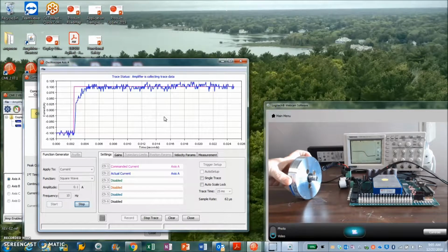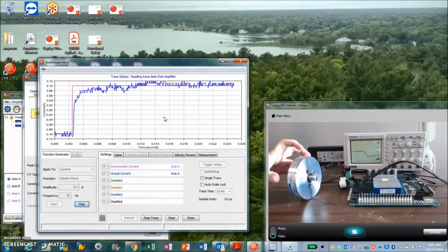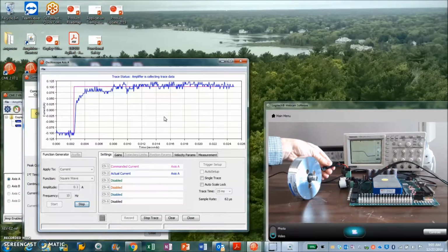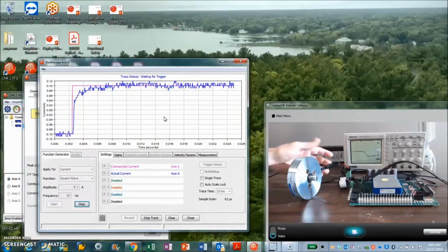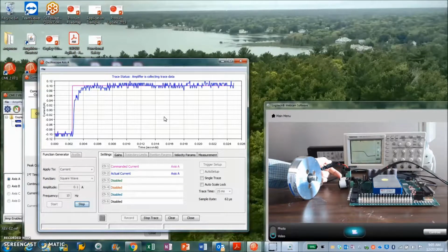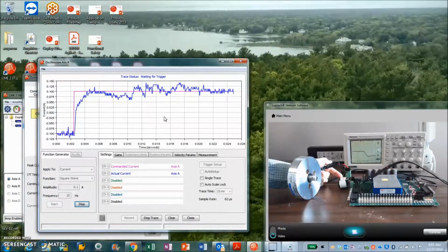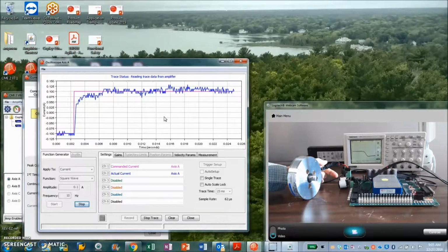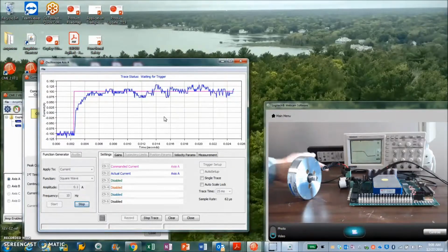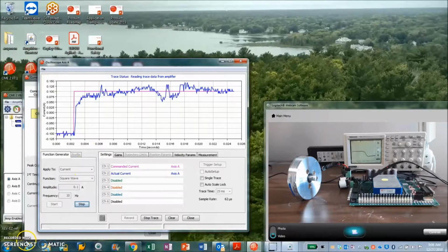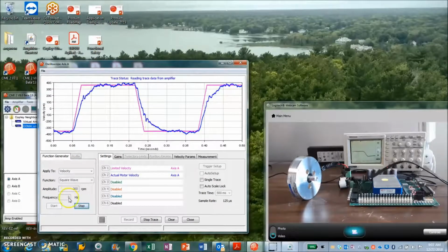You know, you've got to put the case of the motor to ground, but you still have capacitance between the PWM and the cable, and the coil to the case capacitance. So PWM frequencies, high frequencies, tend to squirt out of these areas here, whereas the Copley is considerably quieter. And of course, we have some inductors here, so you know that will slow the rise time down even more at the output. And this is the poor man's filter, so this is very good for low noise and emissions, especially around very susceptible equipment. And you know, the current loop tuning is good, about 1 kilohertz of current loop bandwidth.